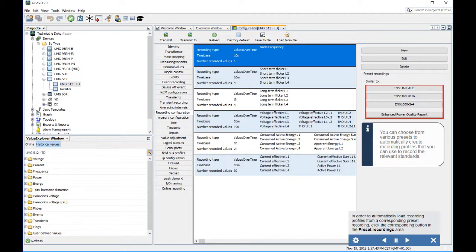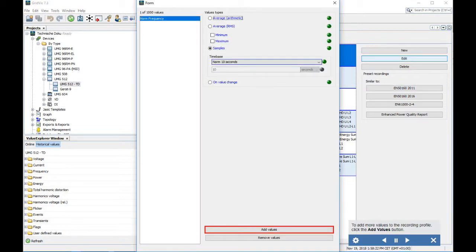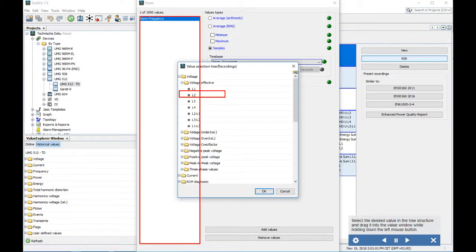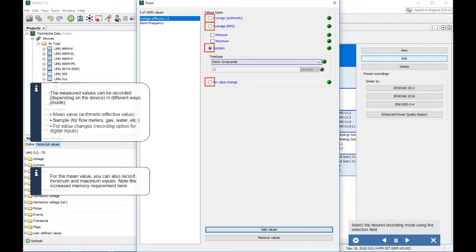You can choose from various presets to automatically create recording profiles that record the relevant standards. To automatically load recording profiles from a preset, click the corresponding button in the Preset Recordings area, then click Yes. Click the Edit button to edit a recording profile. To add more values, click Add Values, select the desired value in the tree structure, and drag it into the value window while holding down the left mouse button. Click OK when done. Measured values can be recorded in different ways: mean value, arithmetic effective value, sample (for flow meters, gas, water, etc.), or for value changes (for digital inputs).